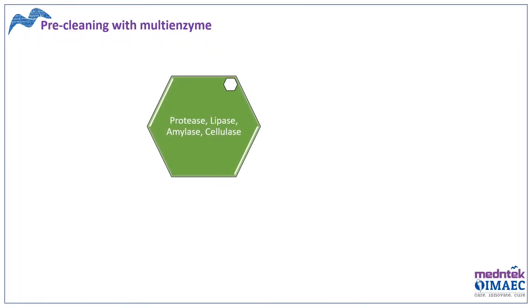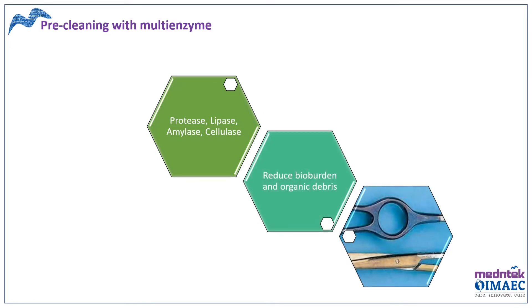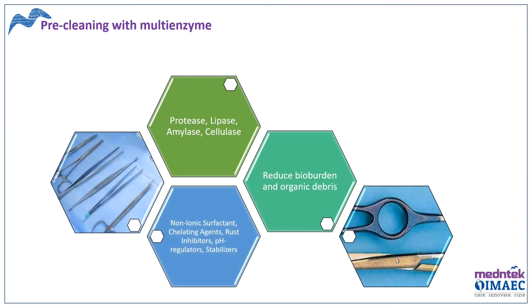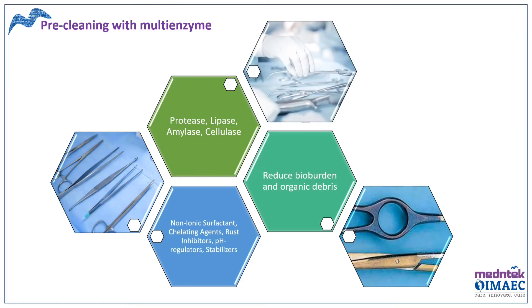Pre-cleaning is the step where the bio-burden of instruments is reduced with the help of multi-enzyme solutions or detergents. In multi-enzyme solutions, protease, lipase, amylase, or cellulase enzymes are used. These inactivate proteins, lipids or fats, starch, and cellulose from the instrument, helping to reduce bio-burden, organic debris, cellular material, and blood components. The solution also contains non-ionic surfactants, chelating agents, rust inhibitors, pH regulators, and stabilizers.